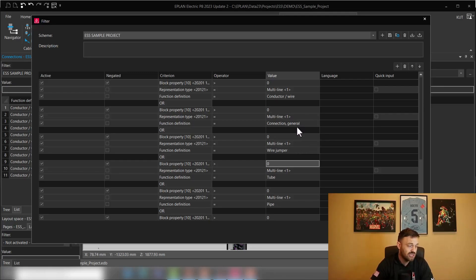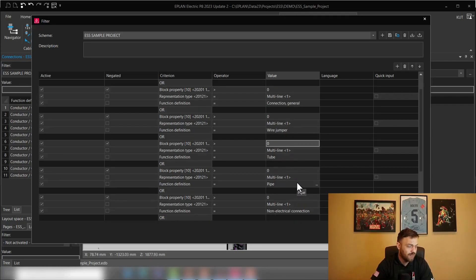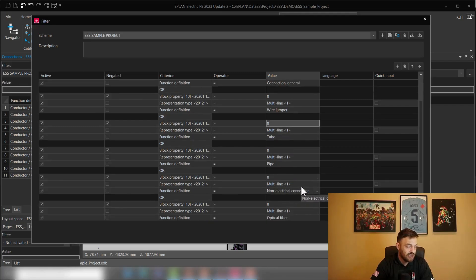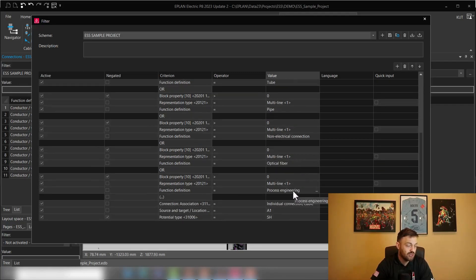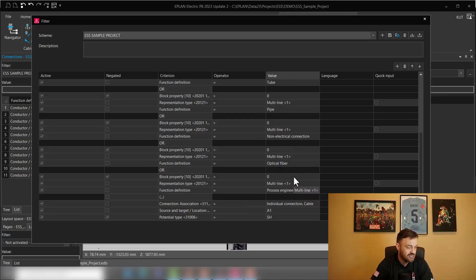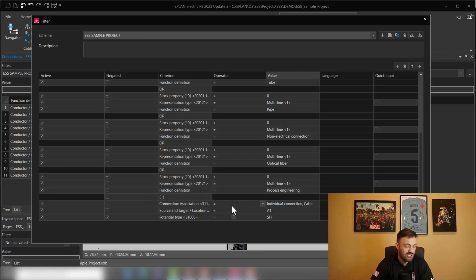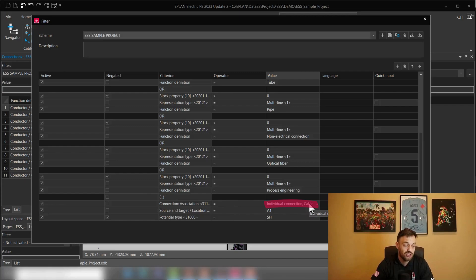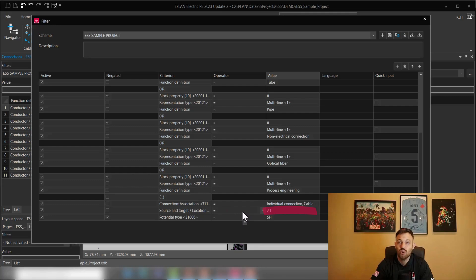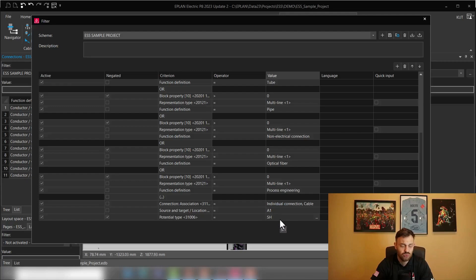We will do the same thing here with an OR function for all routable connections or for all routable function definitions like connections, general wire, jumper, tube, pipe, non-electrical connection, optical fiber, process engineering. And at the end, we are adding an OR function functionality here and telling what is the connection association, the individual connection or a cable, source and target location, so inside of an enclosure A1, and what you don't want to see, for instance, shielded functions.